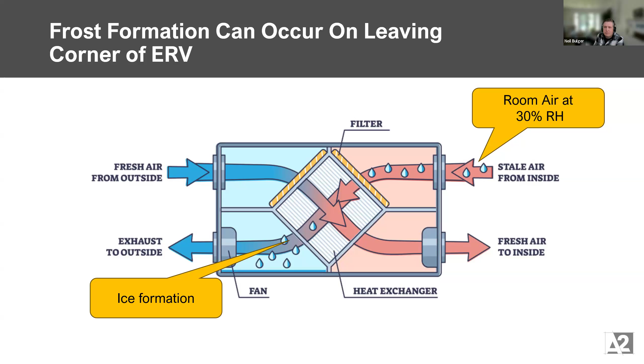So we evaluated this problem from a worst case standpoint: what if a building was maintaining humidity at 30%? When would you get ice forming? The thought is that if you can recover the moisture and pull it back into the building, it won't turn into ice. That's one benefit of an ERV compared to an HRV—in cold climates you can avoid needing to run electric heat to melt the ice off.